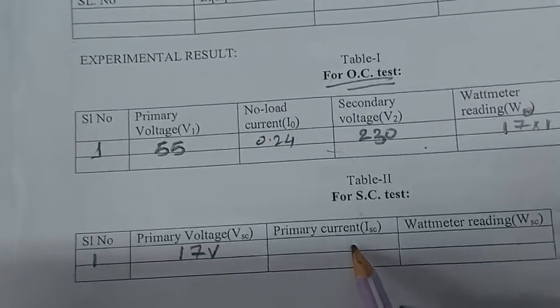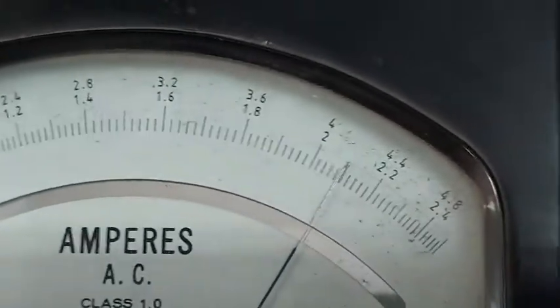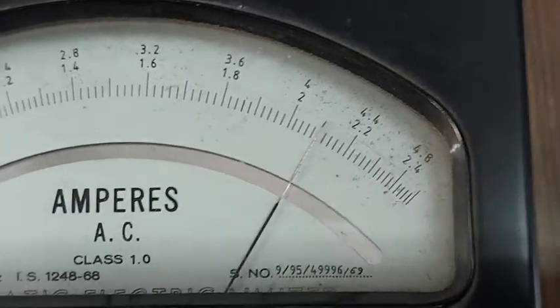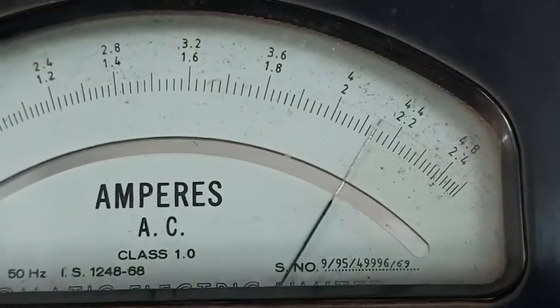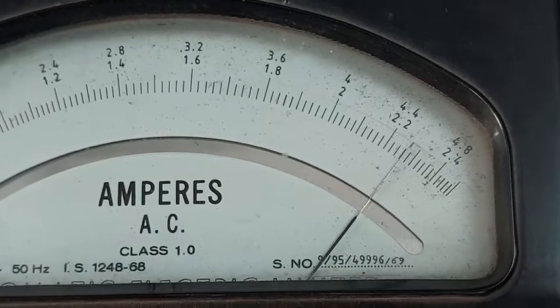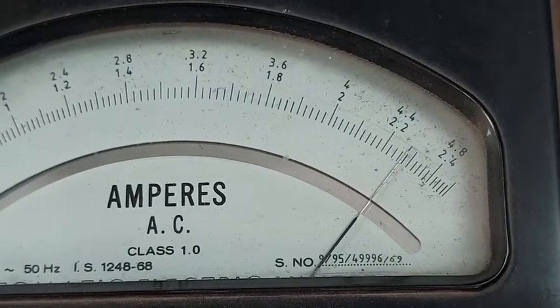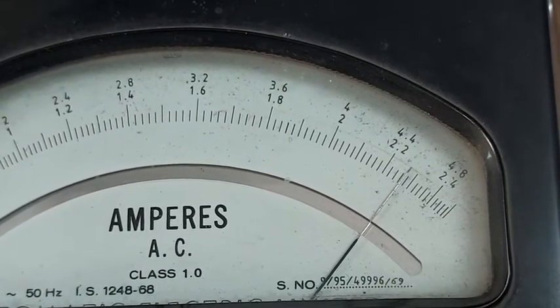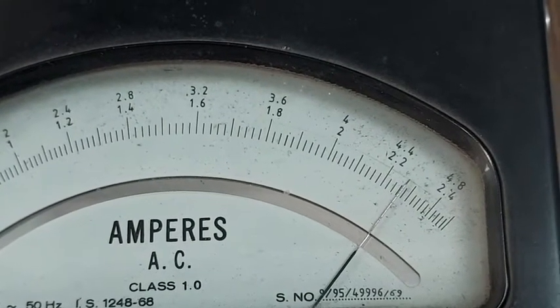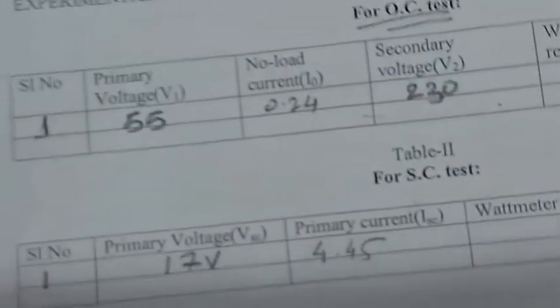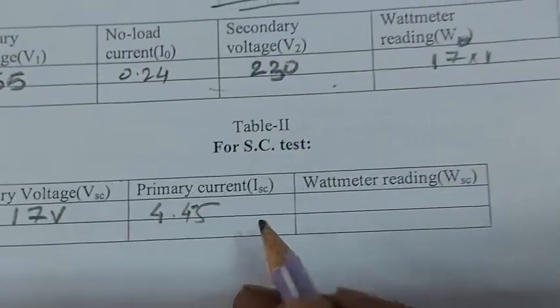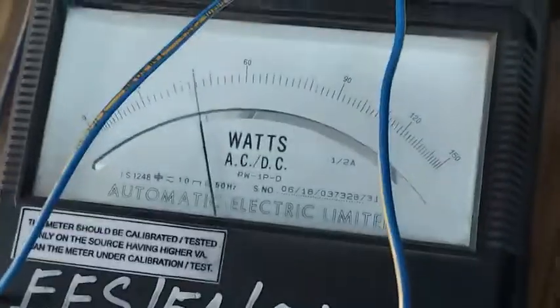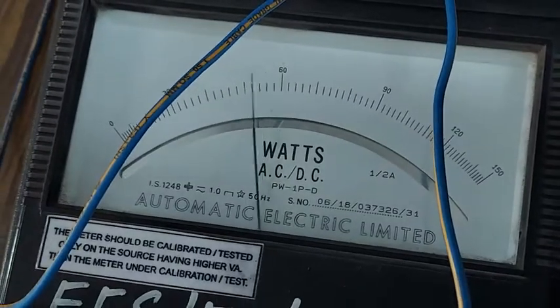Primary current, that is ISC or I short circuit, will be found from this ammeter, which is connected to the 5 ampere range, so we will take the upper scale. So it is 4.4 and then 4.45. It is approximately 4.5, but we will write 4.45. Okay. And after that, the wattmeter reading. The wattmeter reading will be collected from this wattmeter, which is fluctuating a little bit.